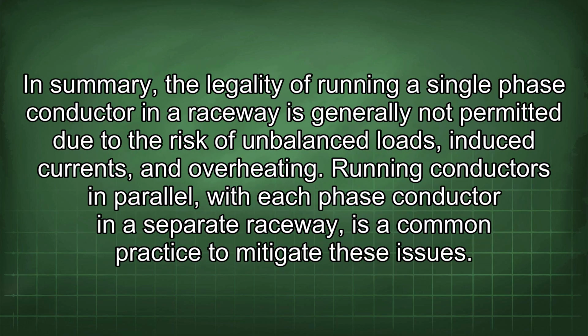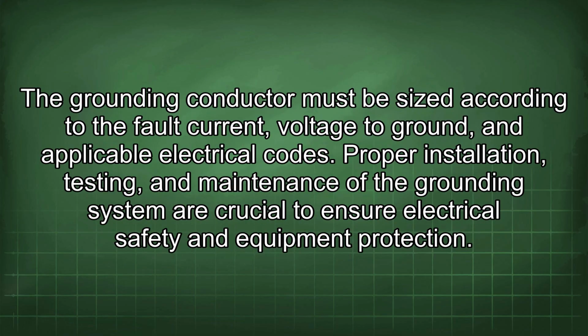In summary, the legality of running a single-phase conductor in a raceway is generally not permitted due to the risk of unbalanced loads, induced current, and overheating. Running conductors in parallel with each phase conductor in a separate raceway is a common practice to mitigate these issues. The grounding conductor must be sized according to the fault current, voltage to ground, and applicable electrical codes. Proper installation, testing, and maintenance of the grounding system are crucial to ensure electrical safety and equipment protection.